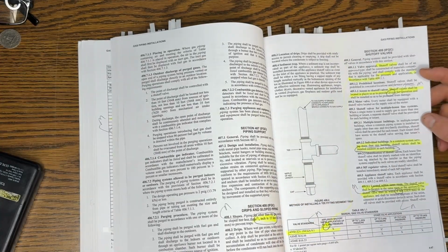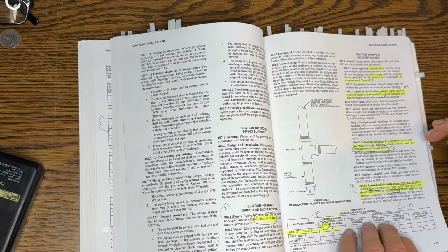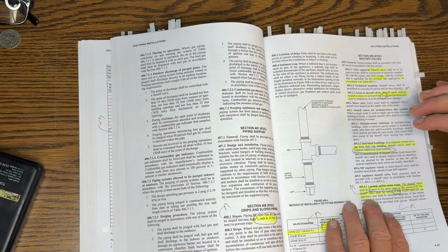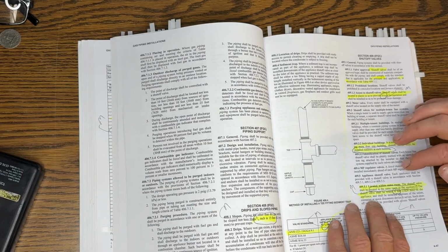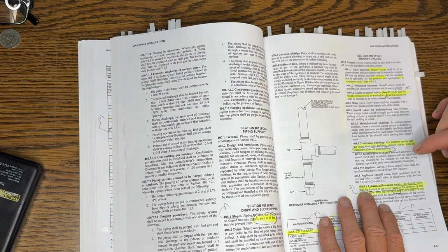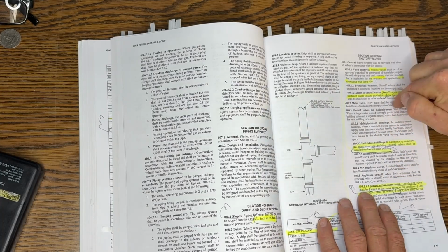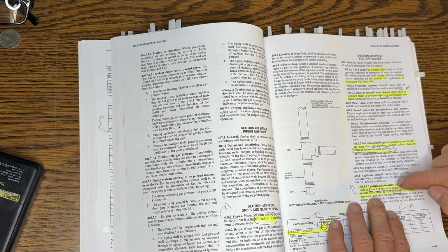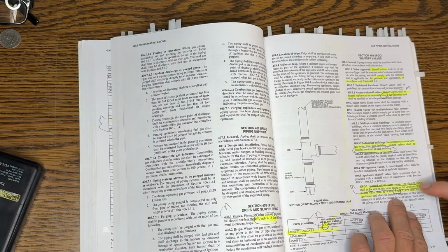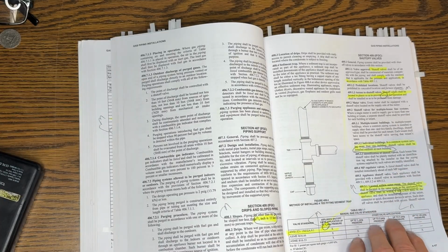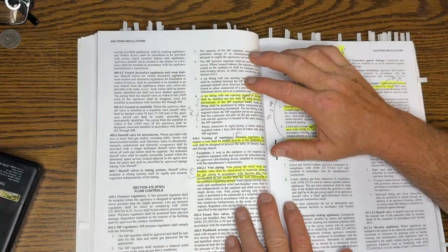Okay, so where do shutoff valves have to be? In a common system serving more than one building, shutoff valves shall be installed outdoors at each building. So if you have multiple house lines, it's outside. And if you have an appliance shutoff valve, keep in mind, it shall be located in the same room as the appliance, within 6 feet. Those are the two requirements. Okay, that's what they're going to ask you.